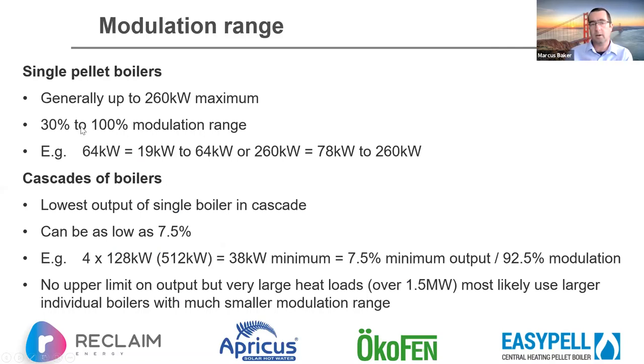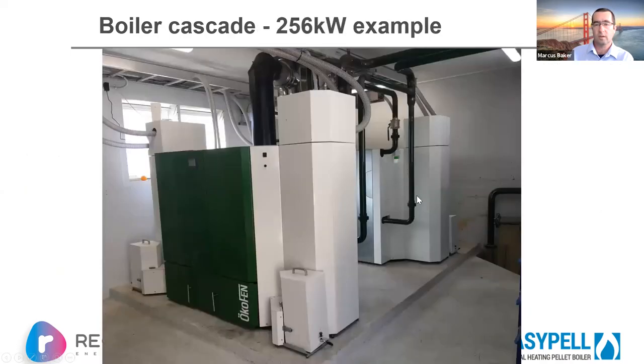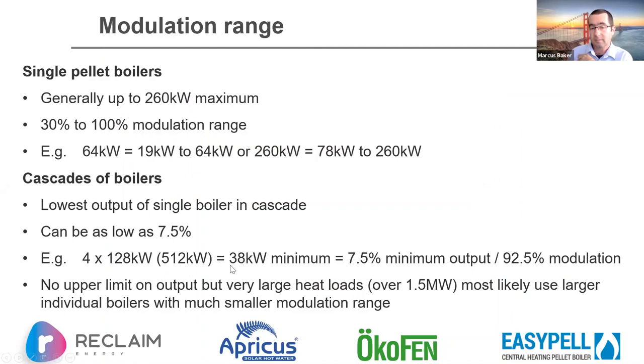Looking at modulation generally, 30 percent is typically the minimum output across boilers up to 260 kilowatts — so for an Ökofen 64-kilowatt unit, you go from 19 up to 64 kilowatts. For cascades, the minimum is only 38 kilowatts from a 500-kilowatt system, giving a huge modulation range — down to about 7.5 percent — which is amazing if you've got very variable heat loading.